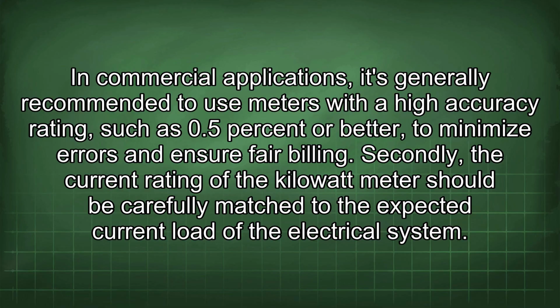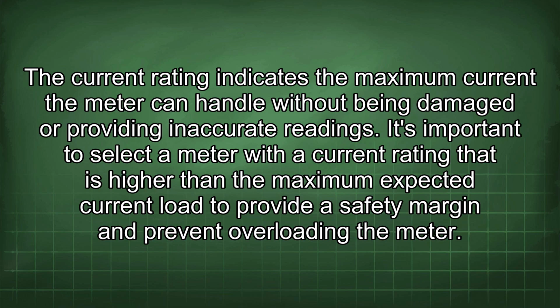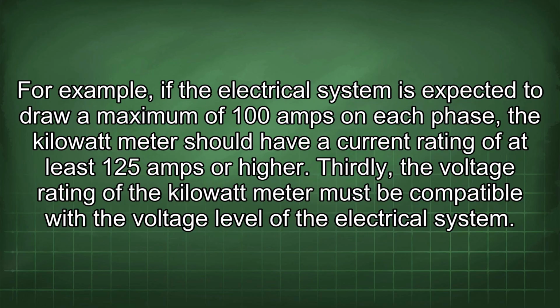Secondly, the current rating of the kilowatt meter should be carefully matched to the expected current load of the electrical system. The current rating indicates the maximum current the meter can handle without being damaged or providing inaccurate readings. It's important to select a meter with a current rating that is higher than the maximum expected current load to provide a safety margin and prevent overloading the meter. For example, if the electrical system is expected to draw a maximum of 100 amps on each phase, the kilowatt meter should have a current rating of at least 125 amps or higher.